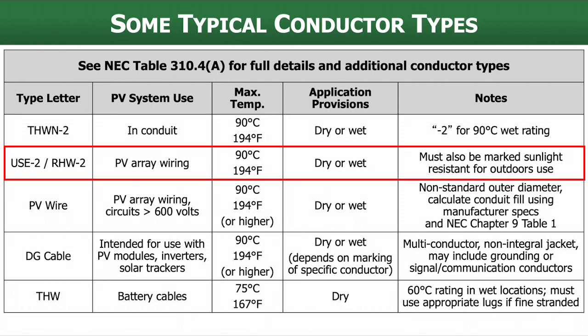USE-2/RHW-2 — that slash means it's dual listed, and you're going to see both of these wire types printed on the conductor itself. As long as this is also marked sunlight resistant, it's really triple listed: USE-2, RHW-2, and marked sunlight resistant. Then we can use this outdoors. It also has a 90°C rating in both dry and wet conditions, and this is something we use for PV array wiring.